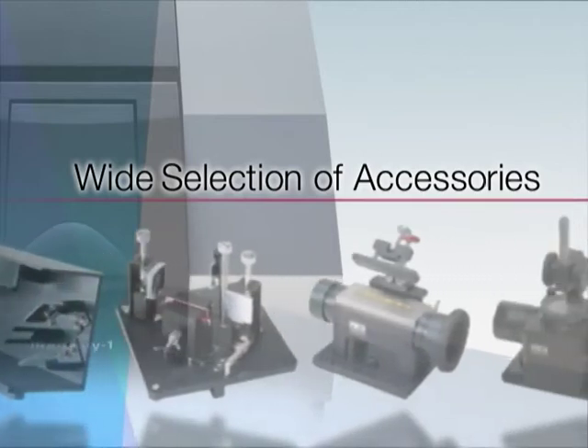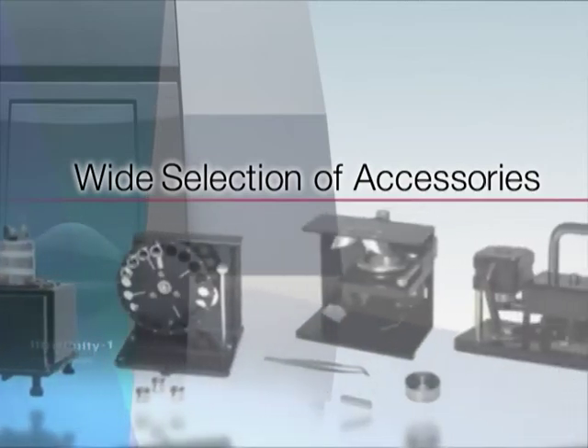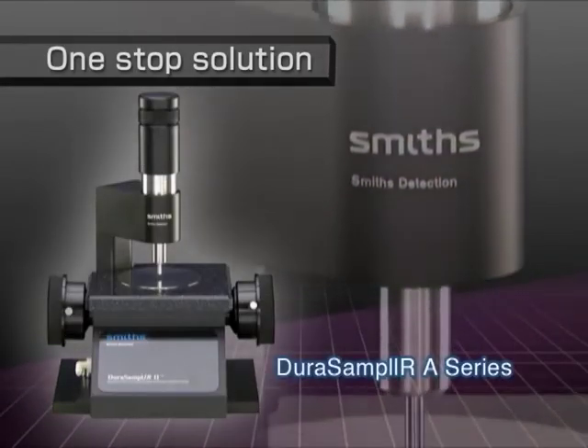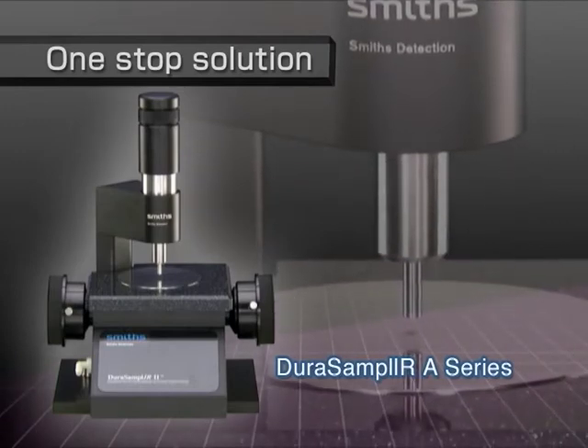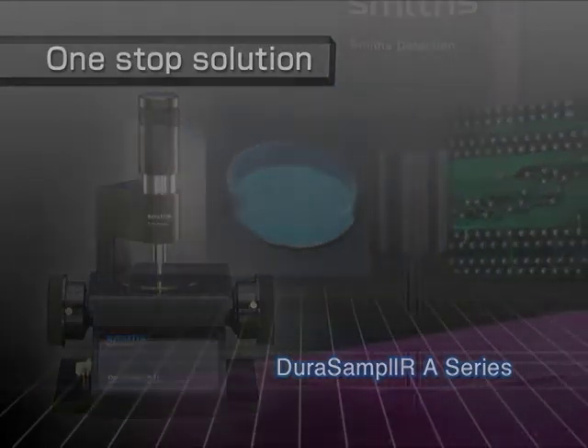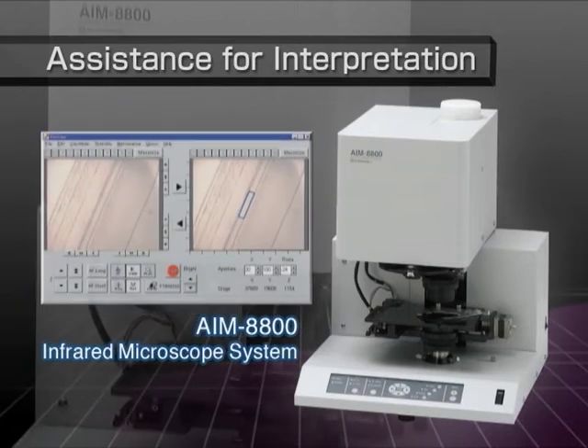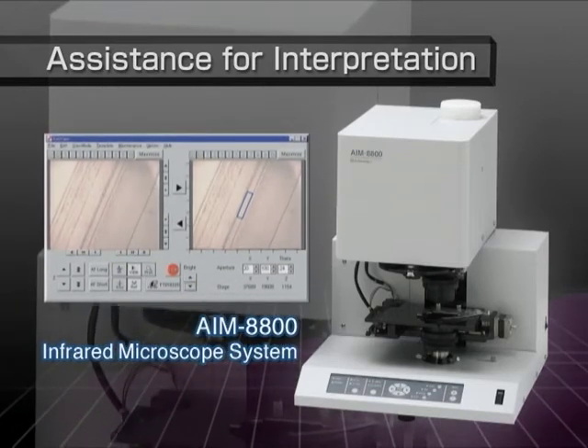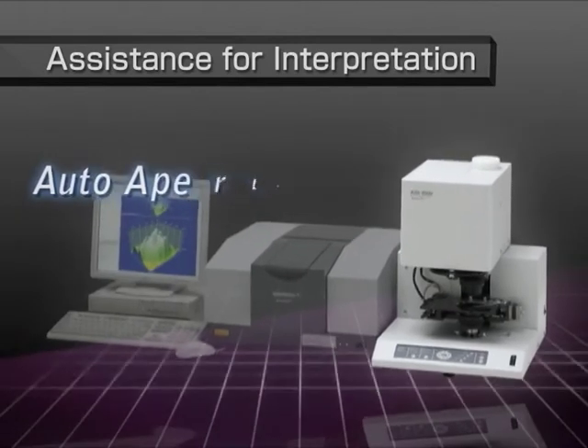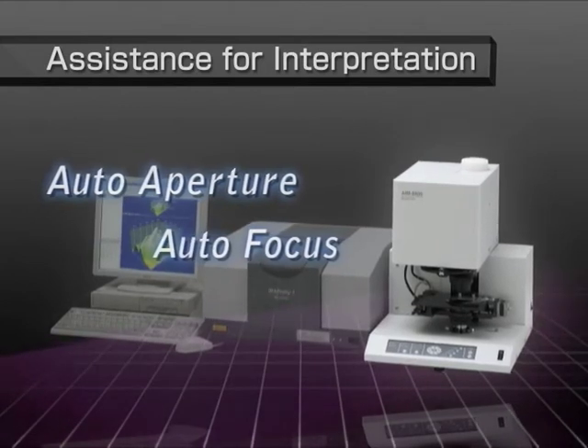IR-Affinity-1 provides a wide selection of accessories for measuring a variety of sample shapes. Since the single reflection ATR and DuraSamplIR A series use a diamond prism, they can measure not only hard samples, but powder, rubber, and liquid samples as well. The AIM 8800 microscope uses a bright, ideally designed optical system and high-sensitivity MCT detector for high-sensitivity measurement of micro samples. Auto-aperture and auto-focus functions make analysis more convenient and simplify micro-sample measurement.